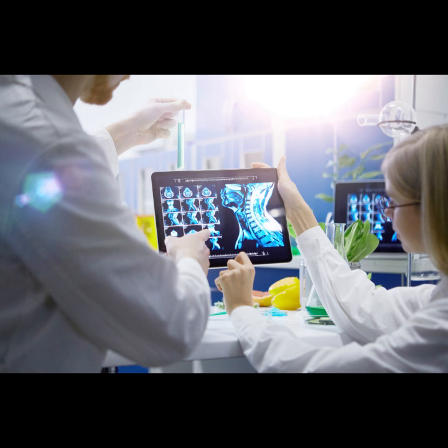And you mentioned the scanner noise earlier, that loud banging. Yeah, it's these gradient coils switching. That's exactly what it is. Smax, the maximum slew rate, is how fast we can ramp the gradients up and down. Gmax is how strong they can be. To map things quickly, we have to switch these powerful gradients incredibly fast.